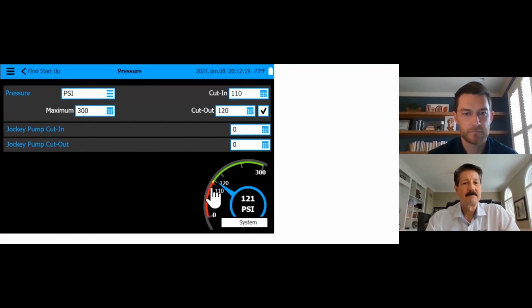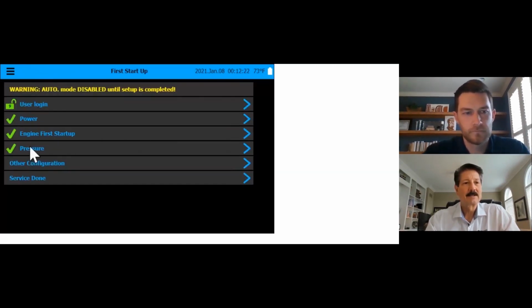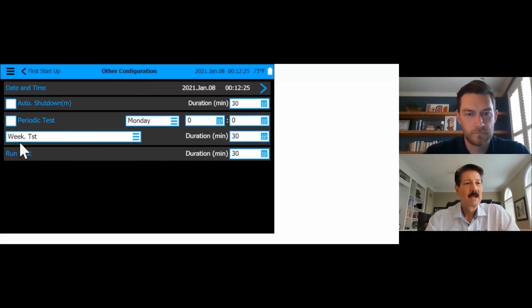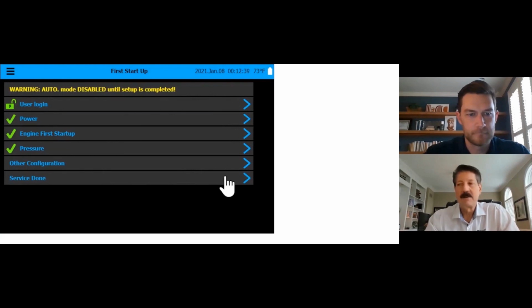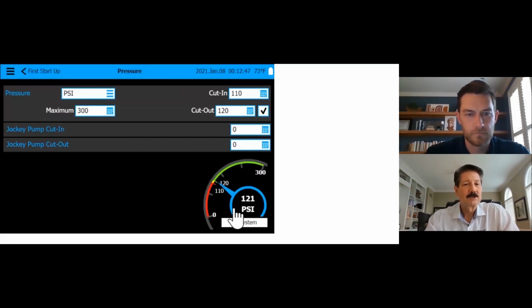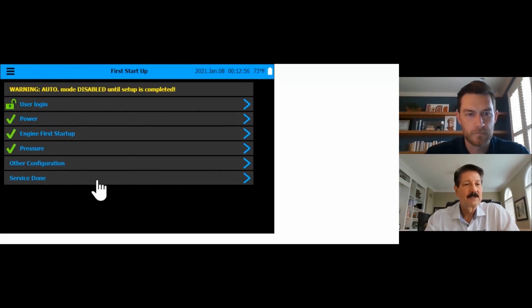So again, everything that you saw on the electric is pretty much the same on the diesel as far as the layout. If I go back to the first start, other configuration here, auto shutdown, we really didn't cover auto shutdown because not very many people do it. There are some. We talked about periodic test, run test, we covered that. And then we hit service done. The most important thing, obviously, is to make sure that the pressure is above the cutout. It is 120 and 121, because if we hit service done and we're below the cut in, it will try to start.